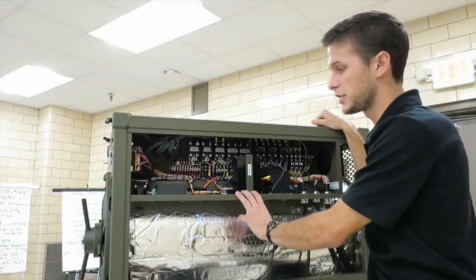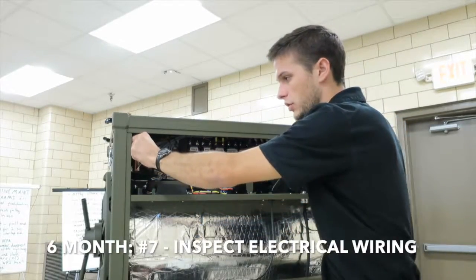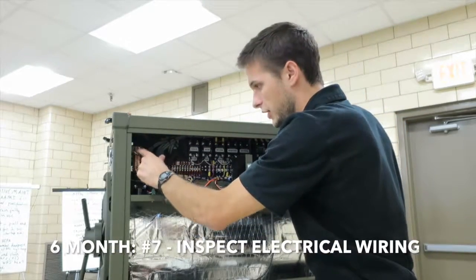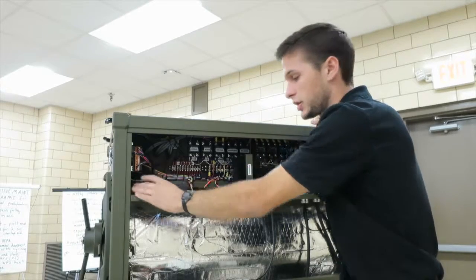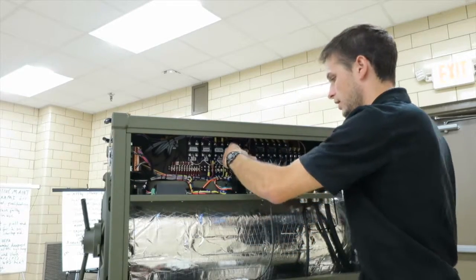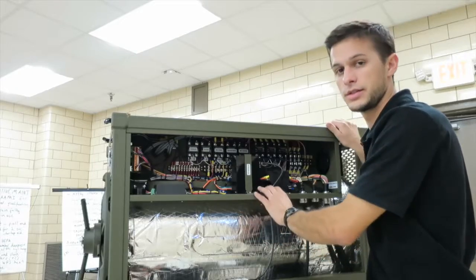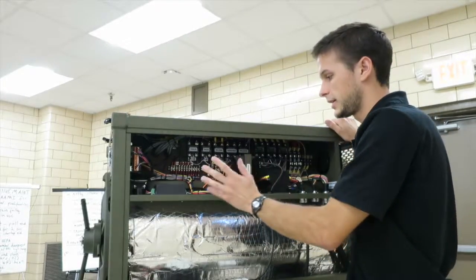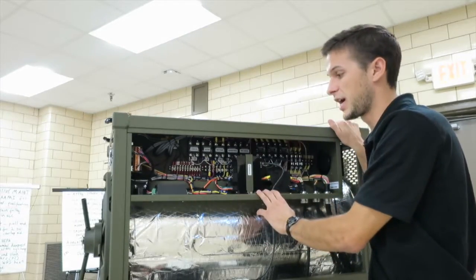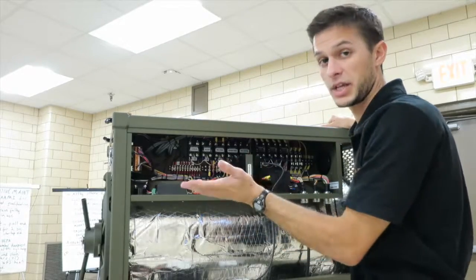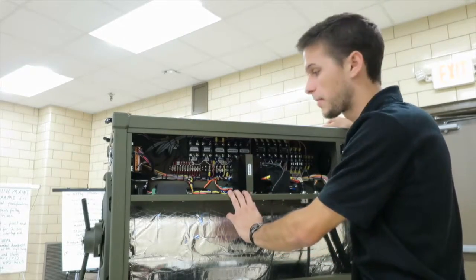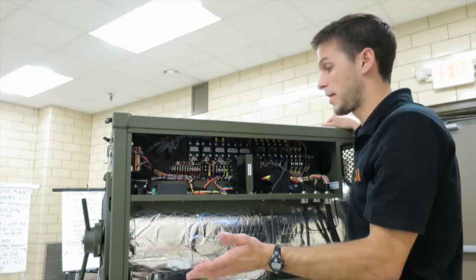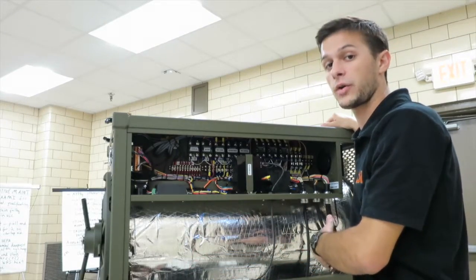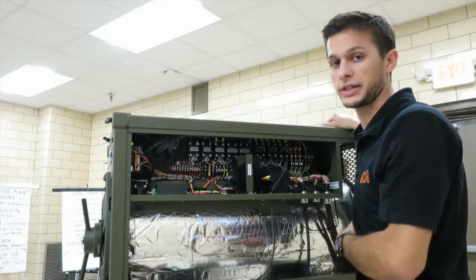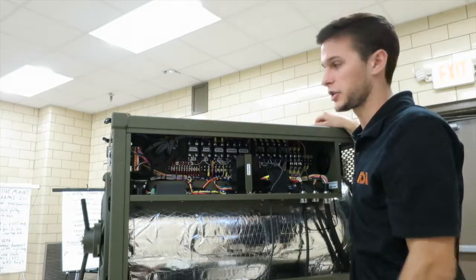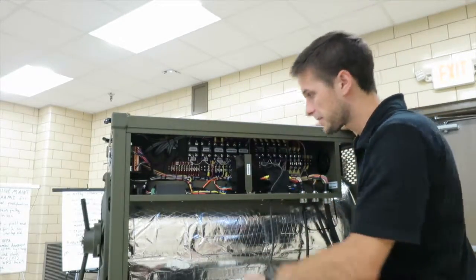Here we have the sterilizer main unit, and again, you can do a light tug just to make sure all the wires are firmly attached to all their connectors. Just make sure everything is firmly attached and not loose. Maybe during transport or over time, some things can become loose. Also, as always, remember to have the unit depowered and completely disconnected. Disconnect the Class L connector before you come into this electrical box.